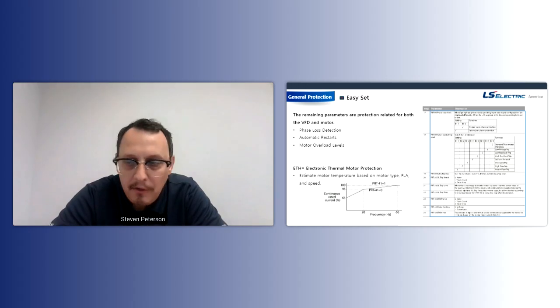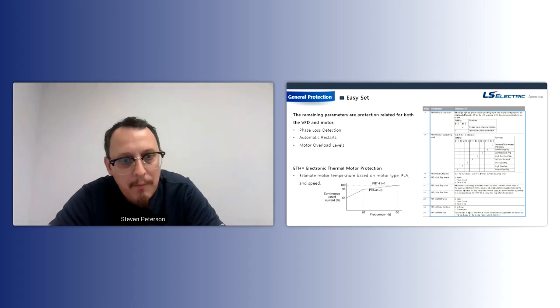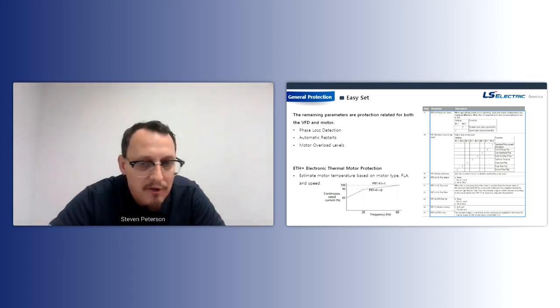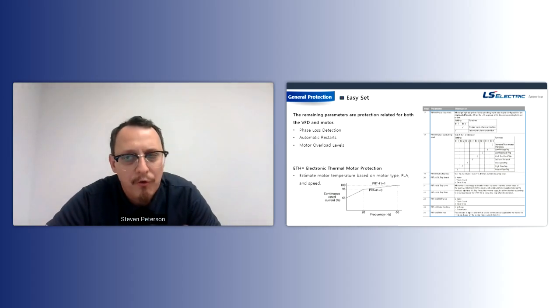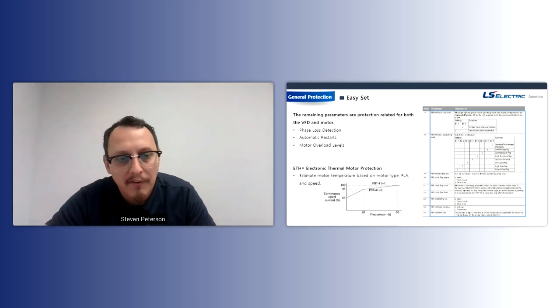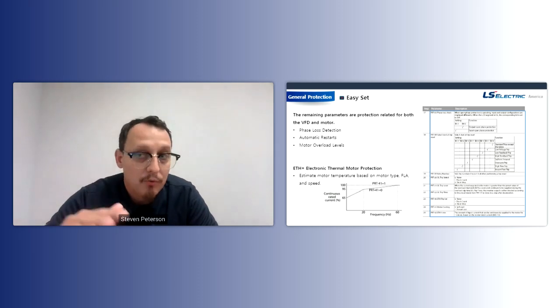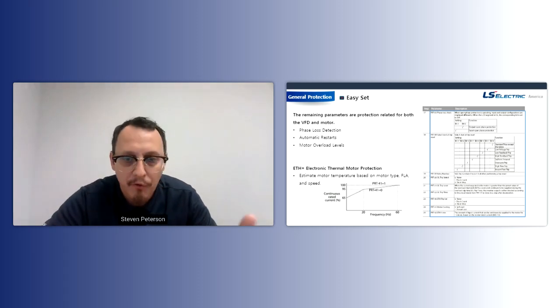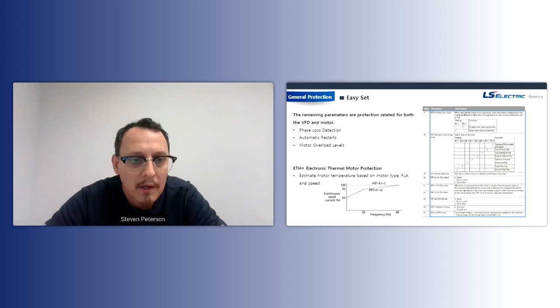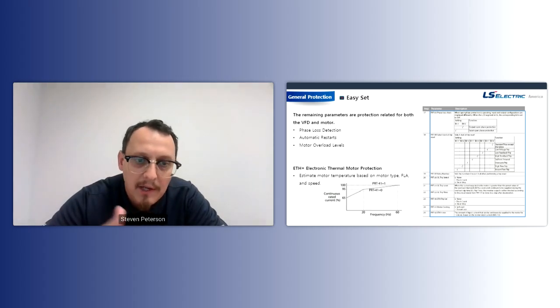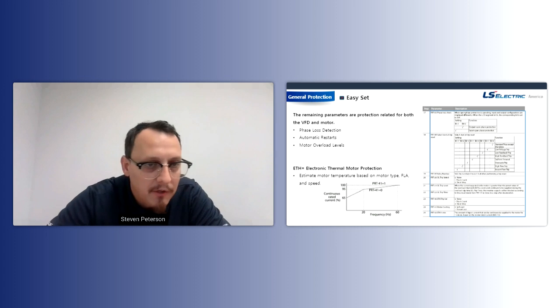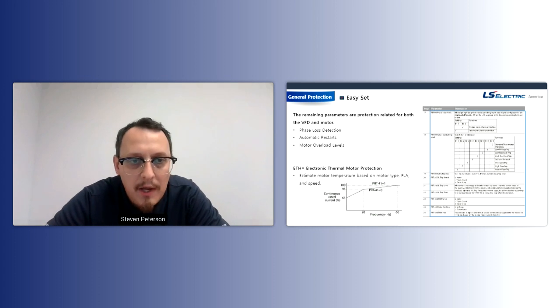So what this does is it estimates the motor temperature based on the motor type, the full load amps you programmed, and the speed. For example, if you look at this bottom parameter here, it says you could change it to force cooled. So force cooled is where you'd have maybe 220 or something running to a fan, so even if the motor is running at a low speed, that fan is running full speed. So you can get a higher current at a lower speed, and technically the motor is being properly cooled. So this is all stuff you guys could adjust. Typically the defaults are okay.